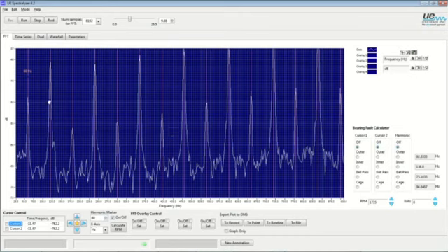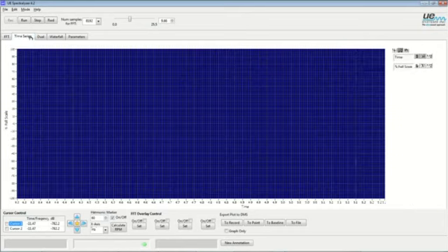And what we see normally, all the 60 hertz harmonics across the spectrum with this transformer hum are very pronounced. The difference is the amplitude. We can see every even number harmonic here has a lower amplitude than the odd number, the 60. Every 120 hertz has a lower amplitude from the other 120 hertz right here. That's characteristic of a transformer.